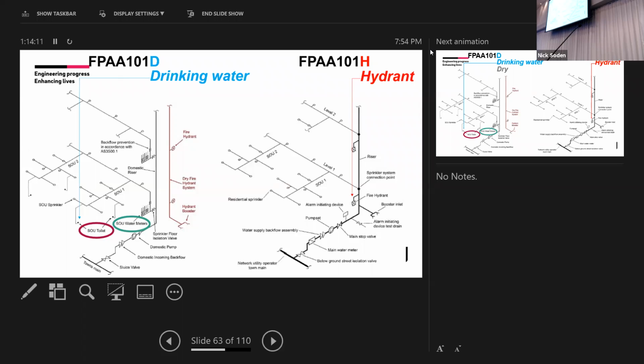Confusion, but unnecessary confusion regarding the demarcation between sprinkler and plumbing trade. And it seems to me that it's only come about because there's this connection to the WC. You might not have the answer to this question, but it's just a general question. So for many, many years, we've had sprinkler systems that are stagnant. And now we're introducing an opportunity to ensure that there's flow through that pipework by virtue of the WC. If that WC wasn't part of this new standard, then the demarcation would stop at the backflow prevention valve and there wouldn't be an issue, right? Plumber plumbs the valve, sprinkler guy takes it off, away we go, happy days, right?